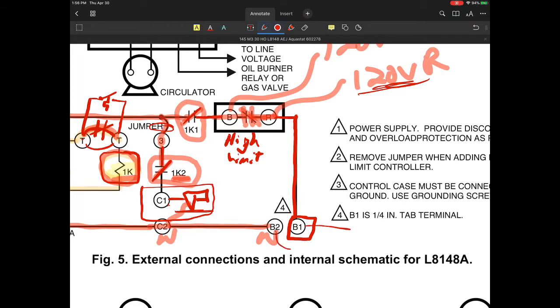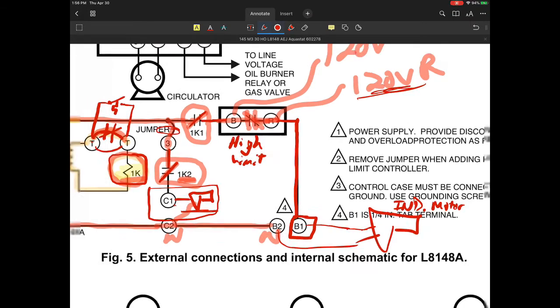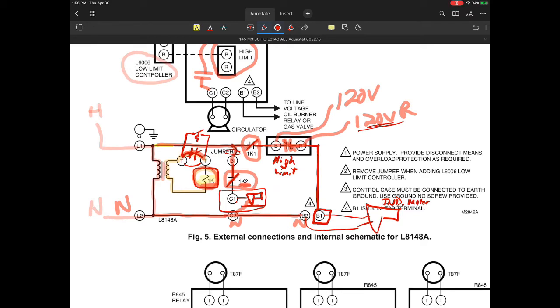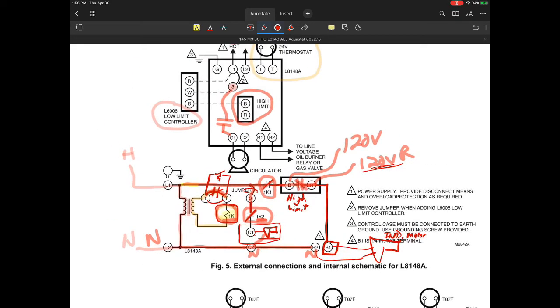Or I had talked about earlier that some of these boilers are power vented. A power venter could very well be powered from B1 and B2 in this situation. So it's very possible that this could be going from here directly to some sort of power inducer motor that would power up 120 if that's an inducer motor. And then of course they might have a 24 volt transformer that is also powered up, and that would provide power to a pressure switch and proof of flow for those systems. So that's primarily what they end up doing. But very simple system when you break it down a little bit.